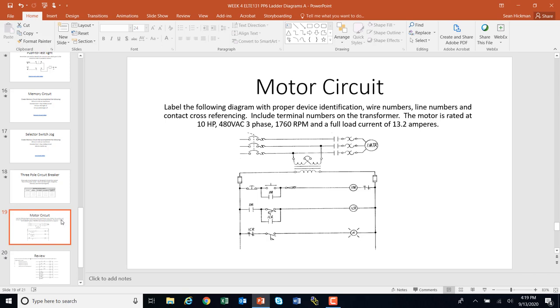Here's a motor circuit. You're going to label the wire numbers and wire the items. For example, this right here is a disconnect — you'll know by looking at it because of the symbol; it's a thermal disconnect. Wire your transformers, wire your overloads, add wire numbers and everything. Take a look at this motor circuit and show it to the lab instructor. Also label your motor: this motor is 10 horsepower, 480 volt, 1760 RPM — those numbers go next to the motor to indicate what you've got.